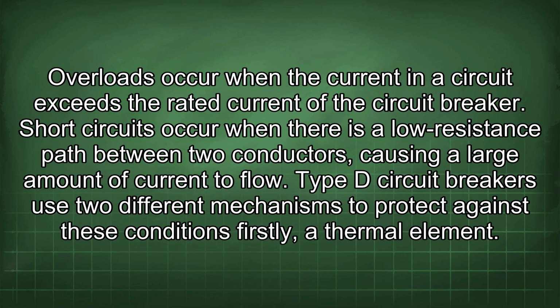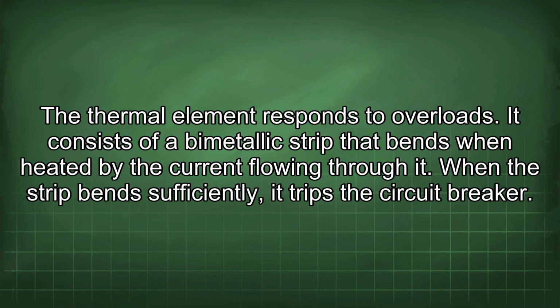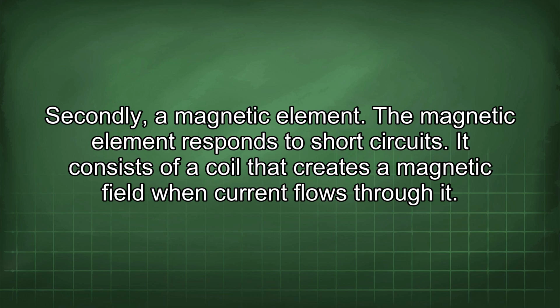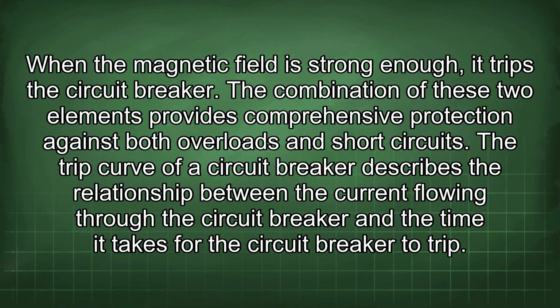Firstly, a thermal element. The thermal element responds to overloads. It consists of a bimetallic strip that bends when heated by the current flowing through it. When the strip bends sufficiently, it trips the circuit breaker. Secondly, a magnetic element. The magnetic element responds to short circuits. It consists of a coil that creates a magnetic field when current flows through it. When the magnetic field is strong enough, it trips the circuit breaker. The combination of these two elements provides comprehensive protection against both overloads and short circuits.